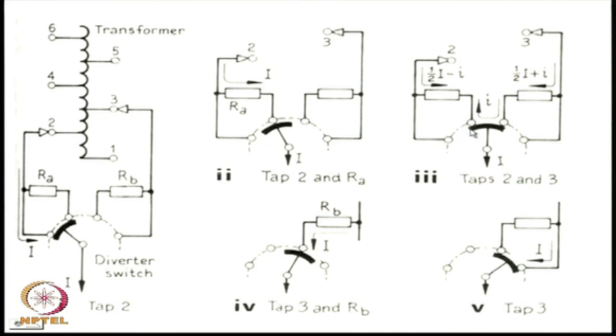Next, we move to this position where tap 2 is completely disconnected and tap 3 is connected through the current limiting resistance R B, and finally, we move here where this R B is shorted by the diverter switch. So, this is the sequence of operation by which one can do online or on load tap changing, that is, without disconnecting the transformer from the load.